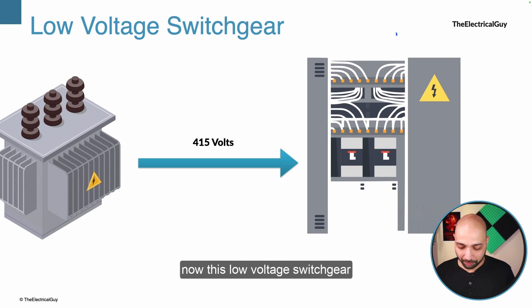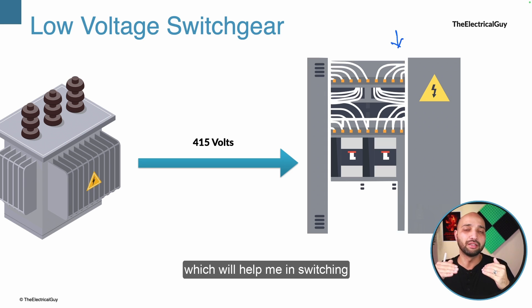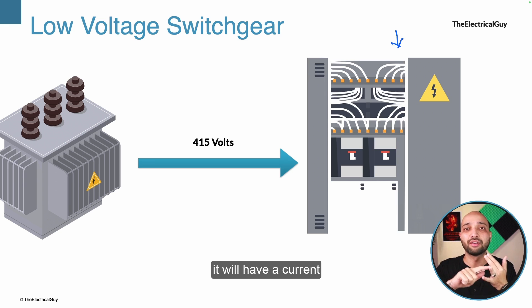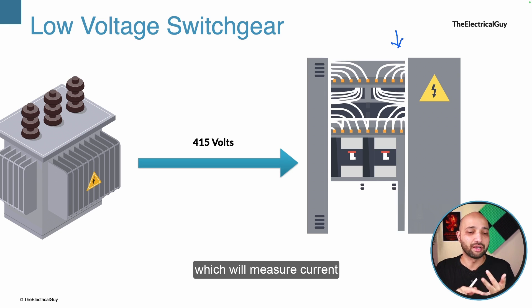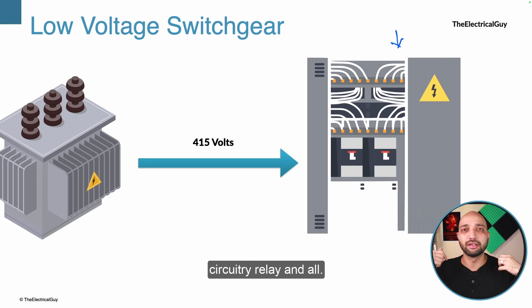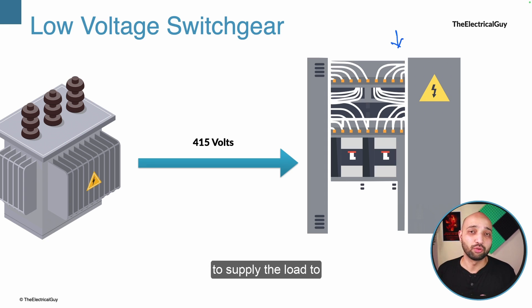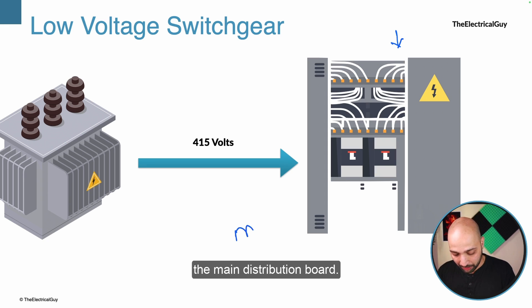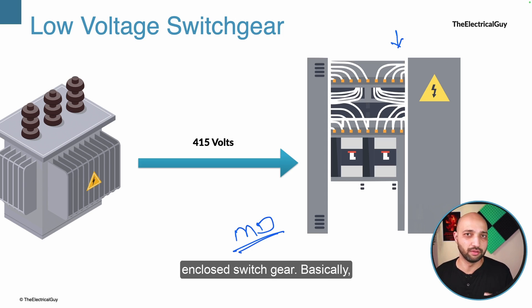This low voltage switchgear panel will have all the necessary components: a main circuit breaker for switching on and off in normal as well as abnormal conditions, a current transformer to measure current, a voltage transformer to measure voltage, plus control circuitry, relays, and more. This panel is necessary to supply the load to the buildings, and we can call it the main distribution board — a metal enclosed switchgear.